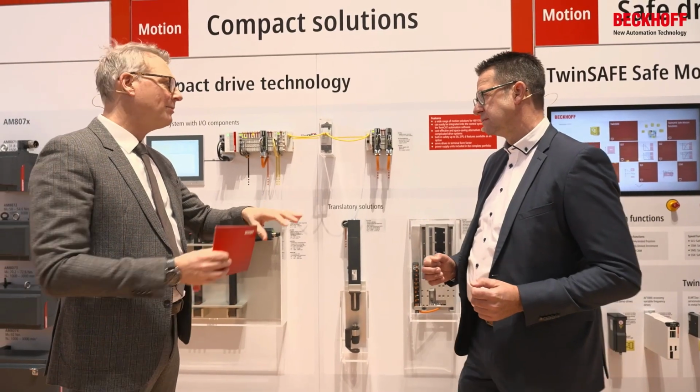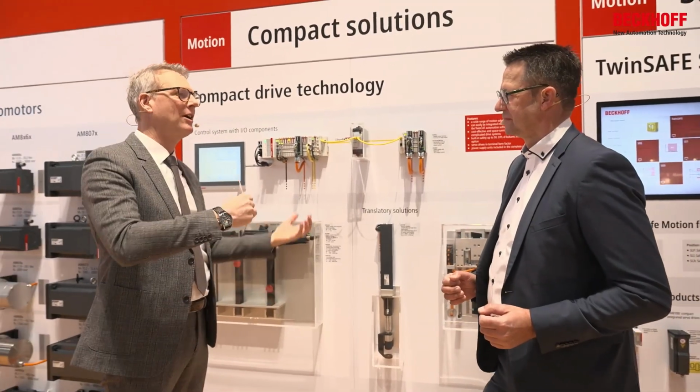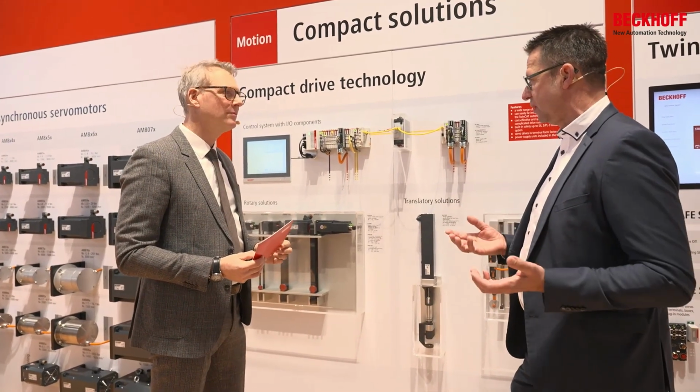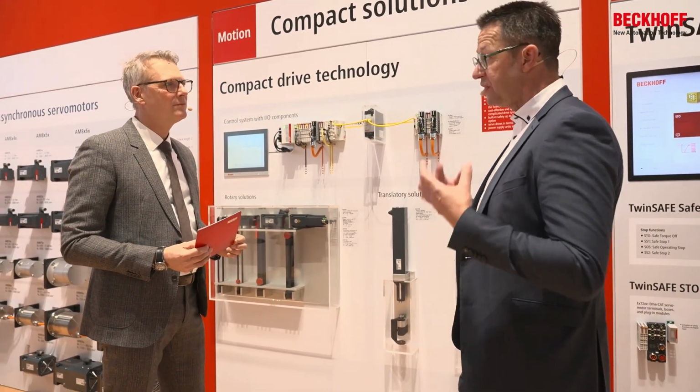Okay, now you have so many years of experience with our support department, our I/O department. Do you have a preference of one or the other? Well, it's not so easy to say because it really 100% depends on the customer application. Because, of course, if you have some temperature problems, dust in your application and so on, it's better to use a central one because then all these electronic components are in a safe environment. So in a central switch cabinet, mostly air conditioned. On the opposite, if you're using this decentralized solution, the motor electronic is directly at the motor. So less cabling, more modular, really flexible if you want to change something in the plant.